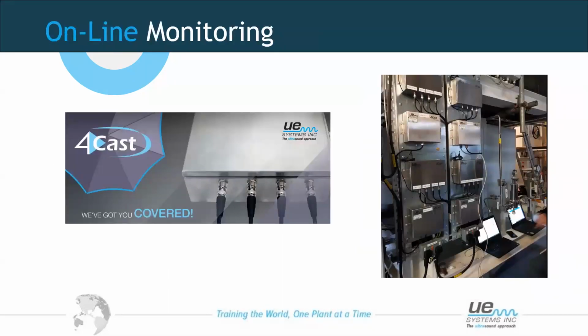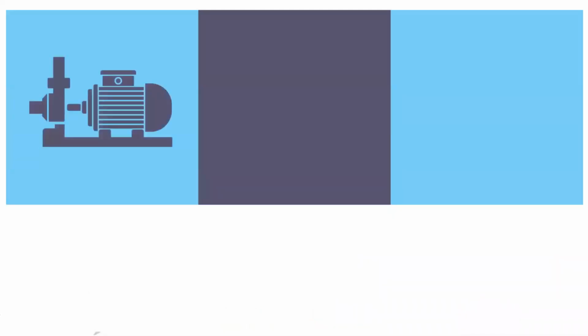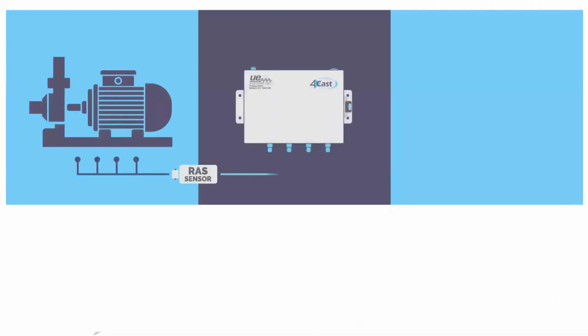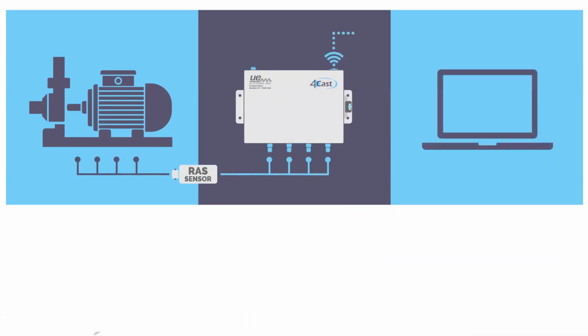So also, there is the need sometimes for online monitoring, depending on how critical the asset is. It's also looking at, do I want to know how soon something's going to fail at the earliest stage, where things like 4Cast systems that are mounted on, we could actually listen to. So for example, you may have your critical asset wired with remote access sensors run into a 4Cast system that can be connected on a network.